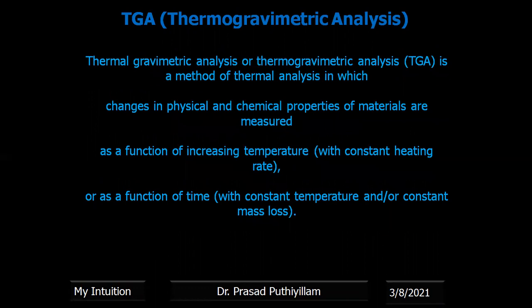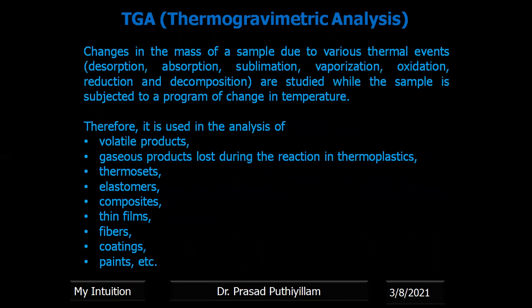TGA or thermo-gravimetric analysis is a method of thermal analysis in which changes in physical and chemical properties of materials are measured as a function of increasing temperature or as a function of time. The various mass changes that can occur by increasing the temperature of the sample may be due to desorption, absorption, sublimation, vaporization, oxidation, reduction and even decomposition.